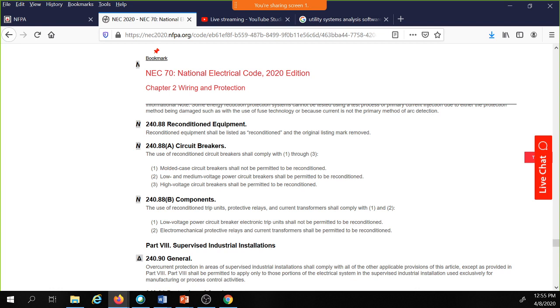So panel 10 went as far as saying, if you're going to recondition a low or medium voltage, or a high voltage breaker, you're permitted to. So Mr. Crusher, if you take that low voltage power circuit breaker and do whatever it is—that voodoo that you do so well—to it, you're going to have to get a third party to list it as being reconditioned.